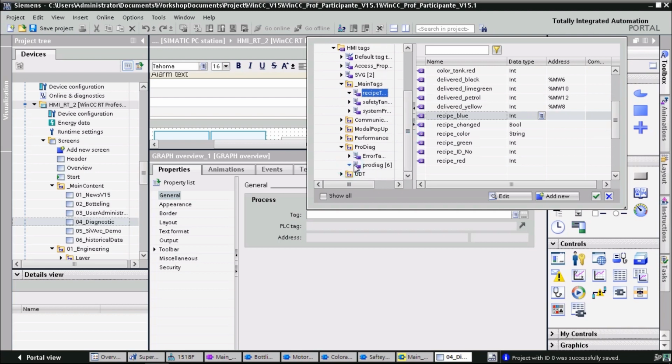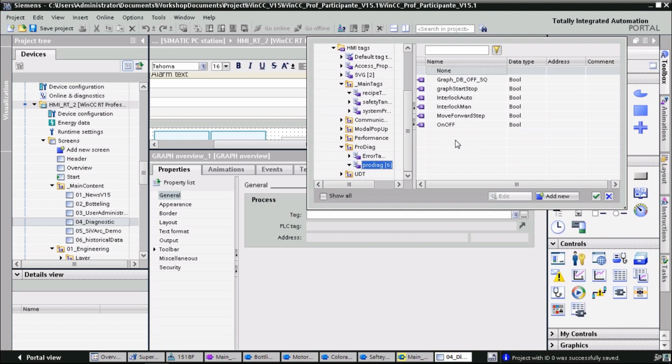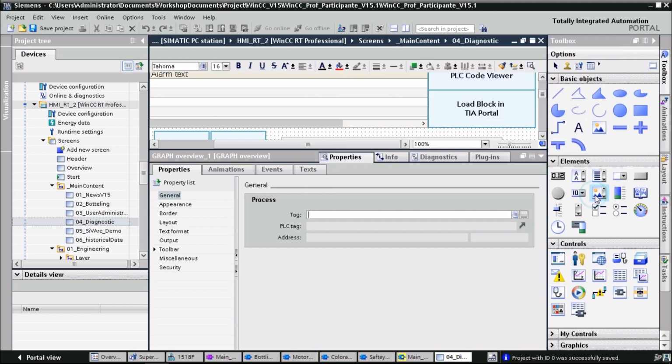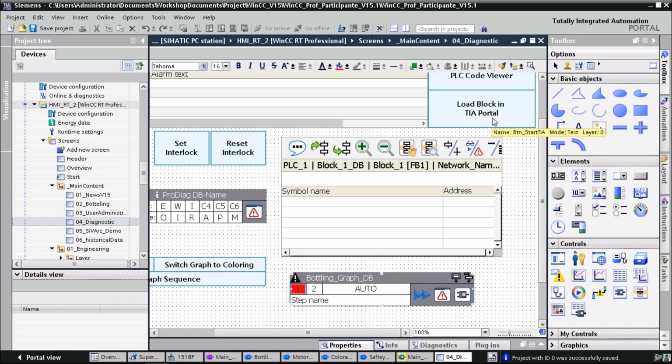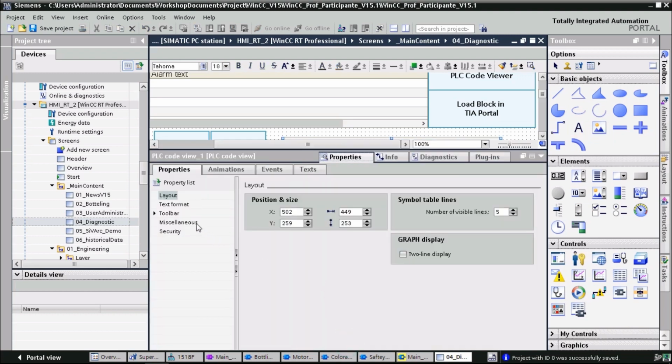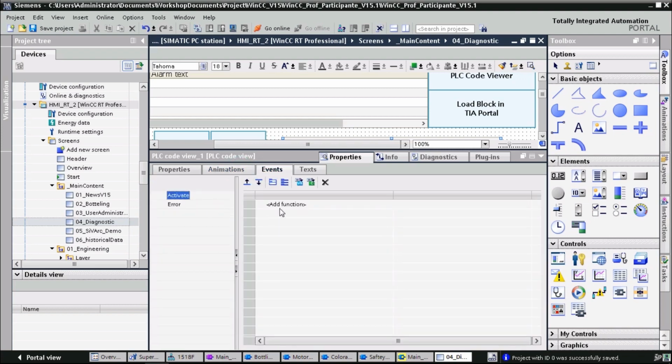We're actually seeing the criteria analysis view with this button here. This exclamation mark shows the first faulty operand. If we switch back to see which operands are all faulty or actually release the start, we see the list here. And if we don't want to see the criteria analysis, we can just deactivate it. And that's it.